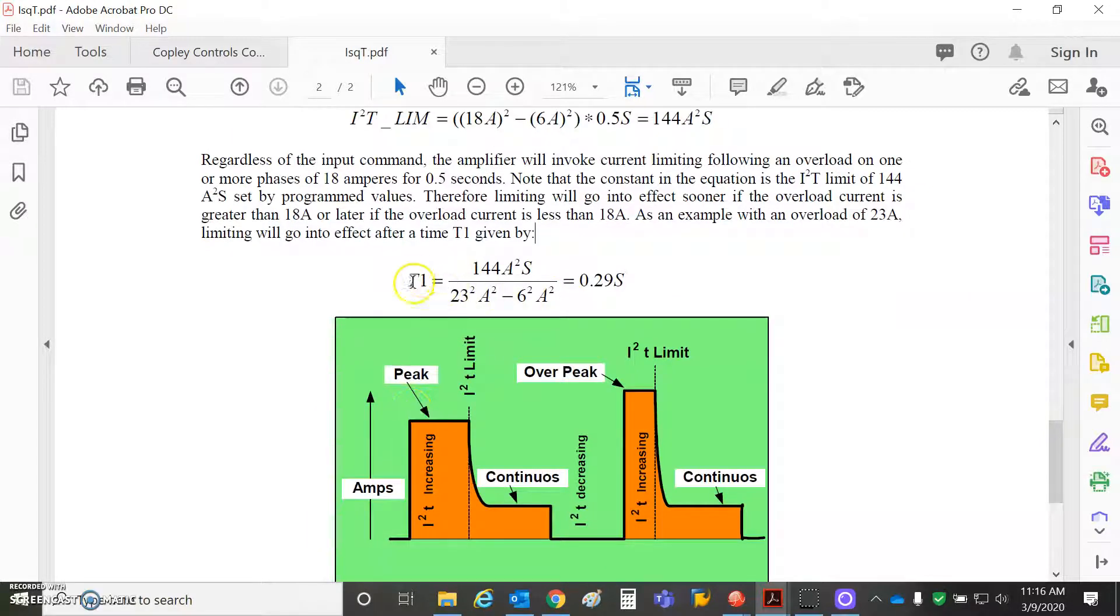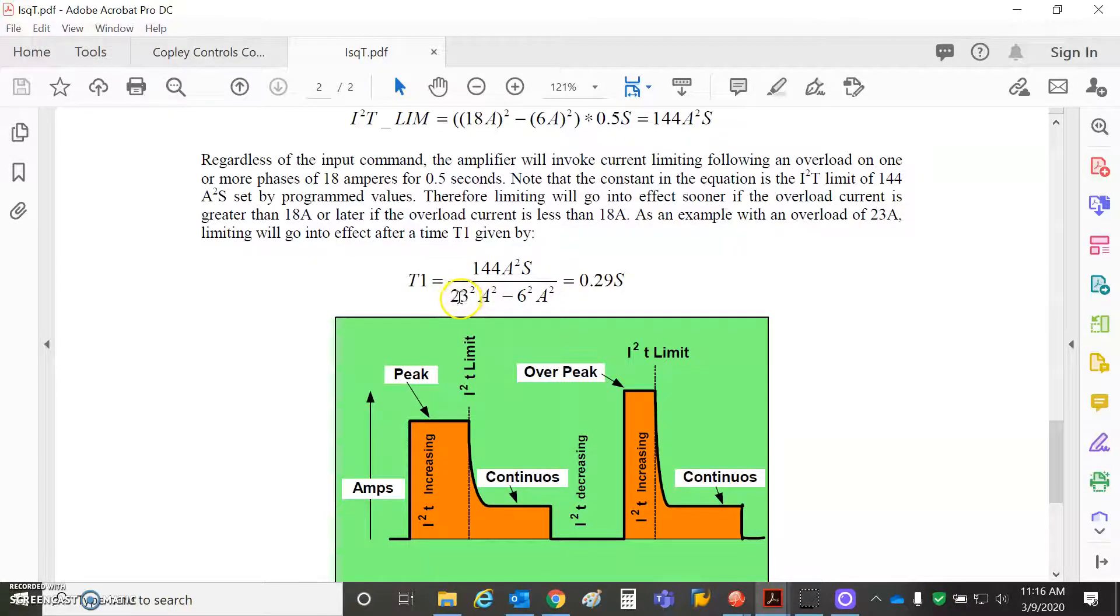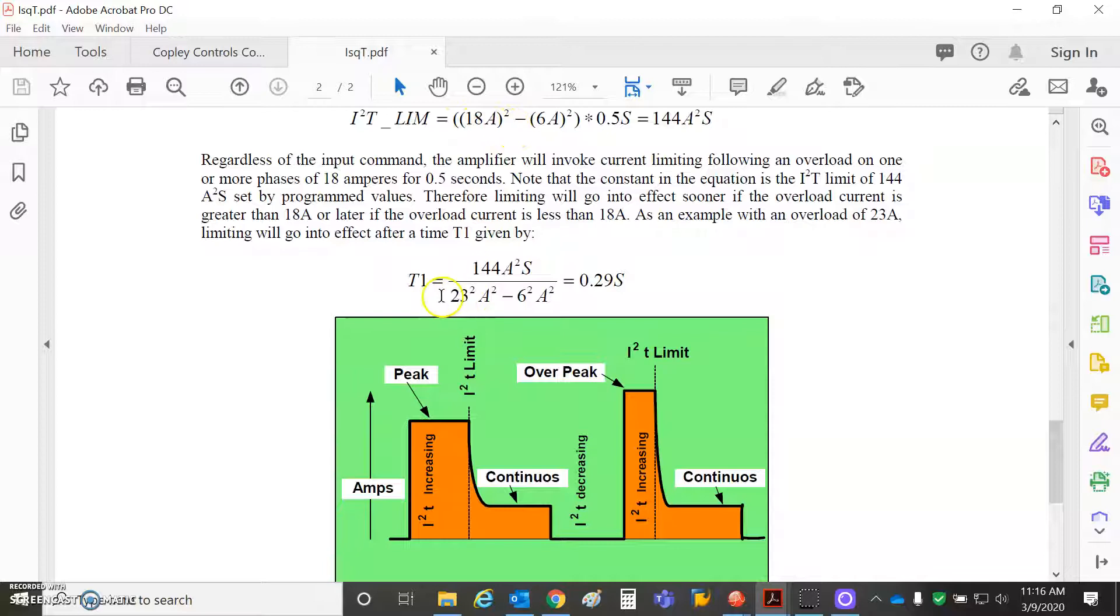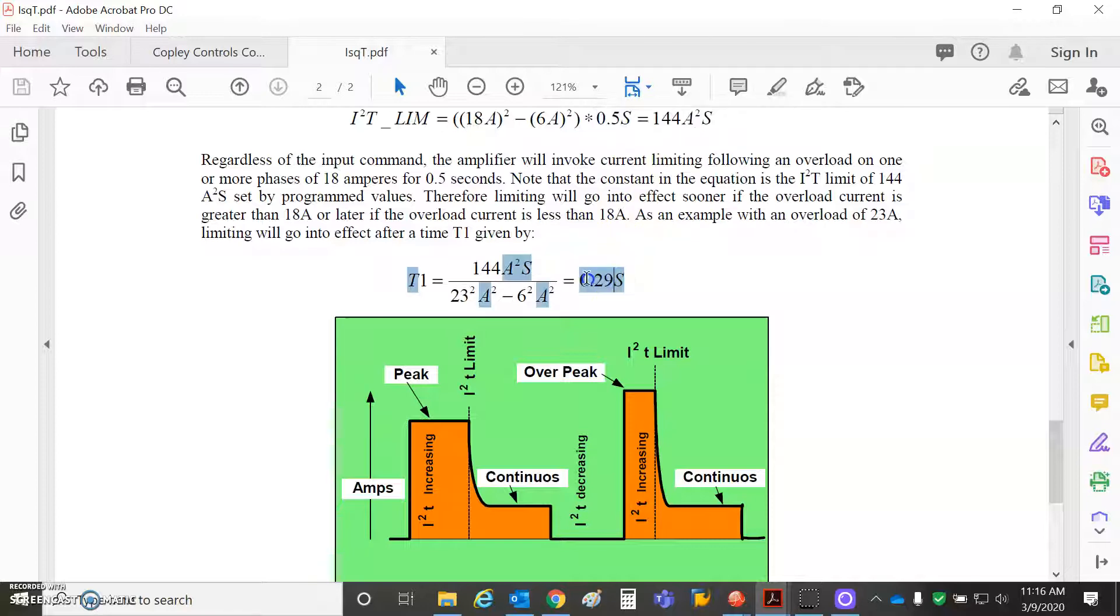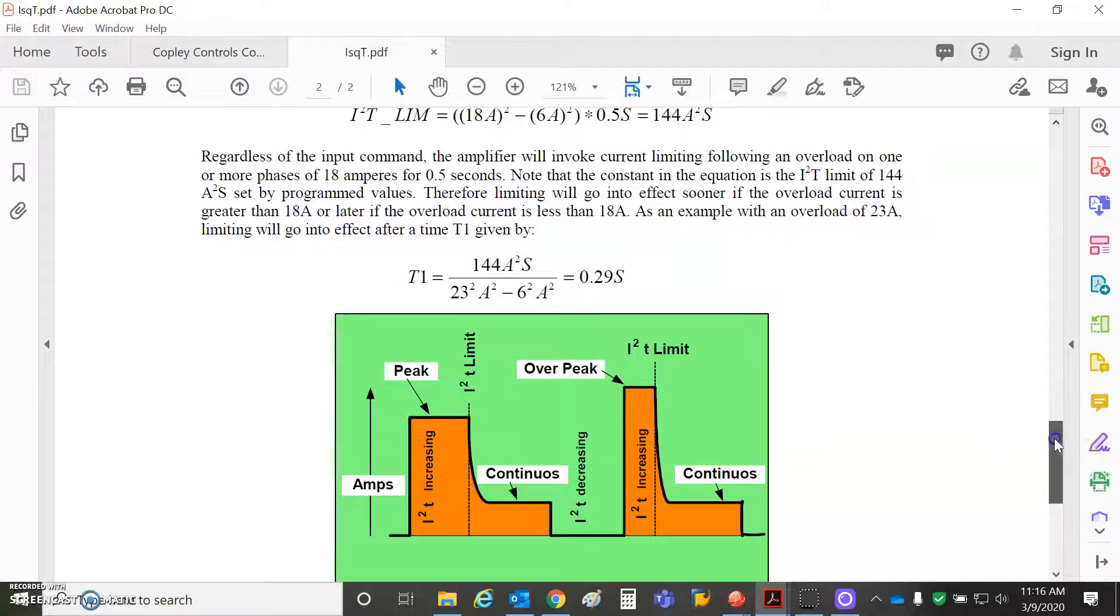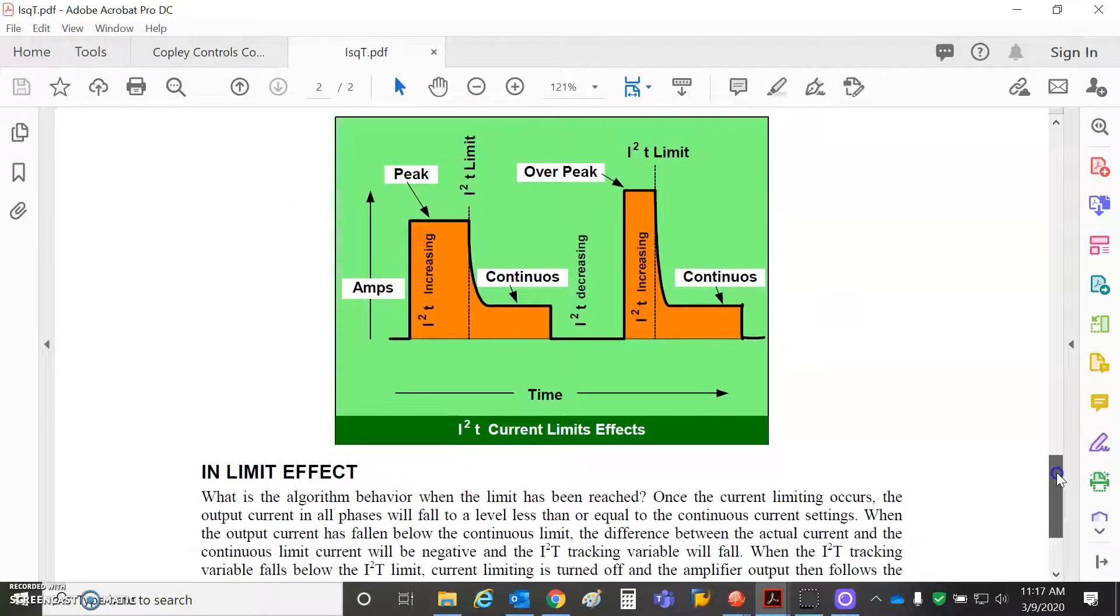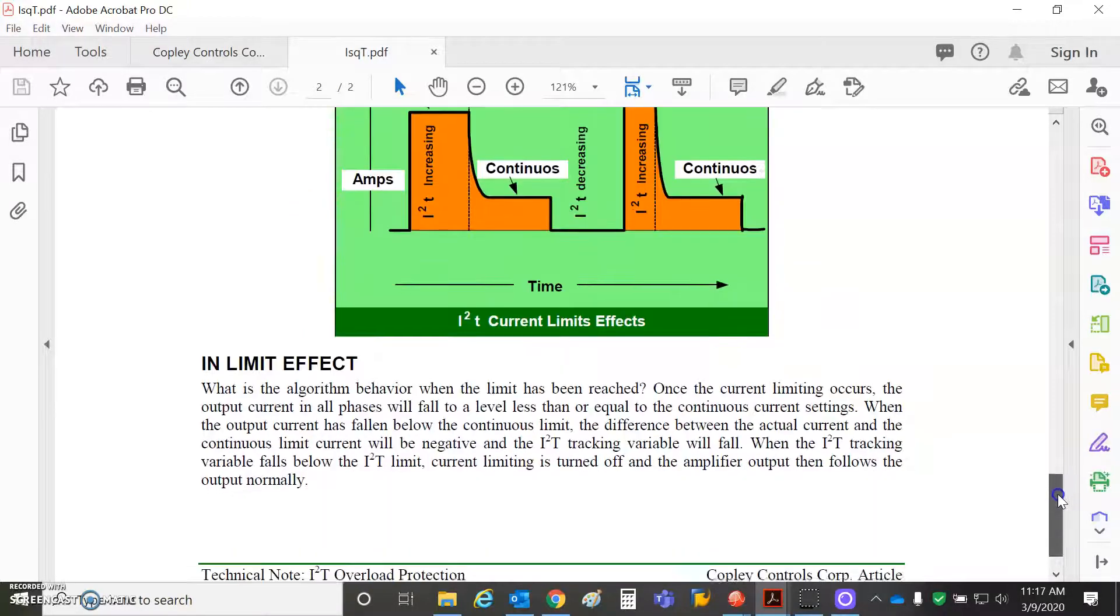That's not peak. Let's say I'm running at 12 amps. How long can I run at 12 amps? Well, it depends on the peak and continuous rating of the motor and the time at that, a second for the bigger motors and hundreds of milliseconds for the tiny motors. And a really large motor might be a couple of seconds. Anyways, you can calculate the time at this lower current. Actually, this one's showing the time if I was at 23 amps. So I'm going way over the current peak to something larger. And it shows me that the time is much shorter. And that's the effective heating of the motor. And so that's what the I squared T limiting is doing in the drive. It's just protecting the motor from overheating.